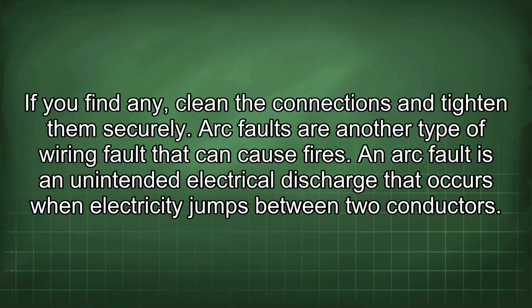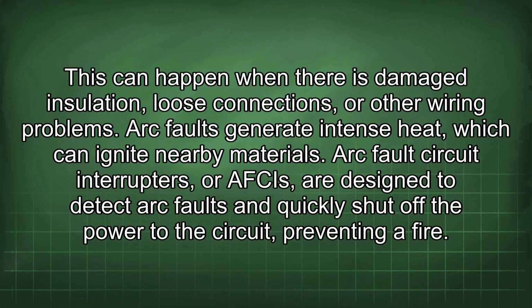Arc faults are another type of wiring fault that can cause fires. An arc fault is an unintended electrical discharge that occurs when electricity jumps between two conductors. This can happen when there is damaged insulation, loose connections, or other wiring problems. Arc faults generate intense heat, which can ignite nearby materials.